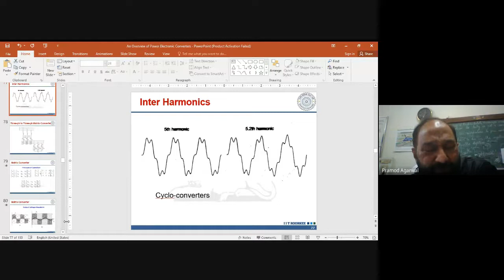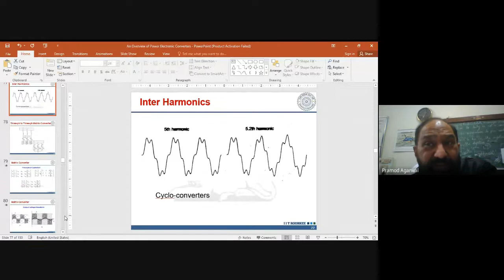But using a cycloconverter, you can only have frequency reduction. And as I said, it can go up to 1/3 maximum of the input frequency. But if you want higher frequency, even more than the supply frequency, then we go for a matrix converter. So here you have the load and the source, and the load is connected to the source through a matrix converter. It is a 3x3 matrix converter, having 9 bidirectional switches.